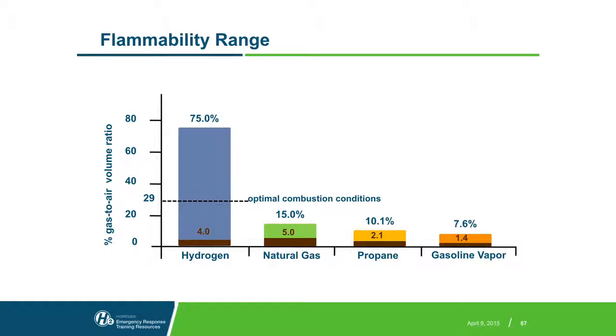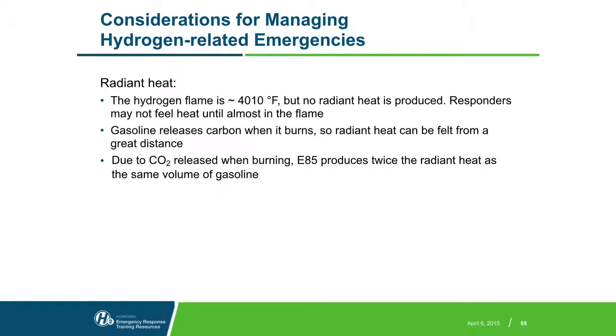with not a very good chance you're going to get to that, given the other elements of the use of hydrogen being in the open air and gas sensors that are calibrated down around this lower flammability limit and even below that. So again, designed to ultimately shut down around 2% and start alarming at levels lower than that. Low radiant heat, as we've talked about. In terms of responders, your thermal imaging cameras can be a useful tool if you suspect that there is flame. Scanning the unit with the TIC could be helpful.